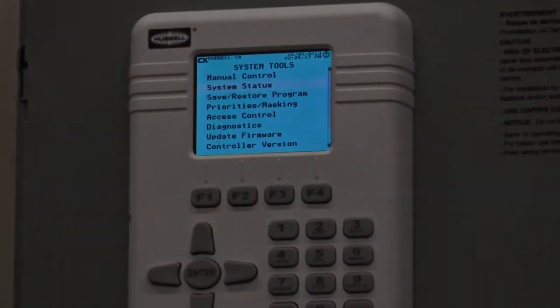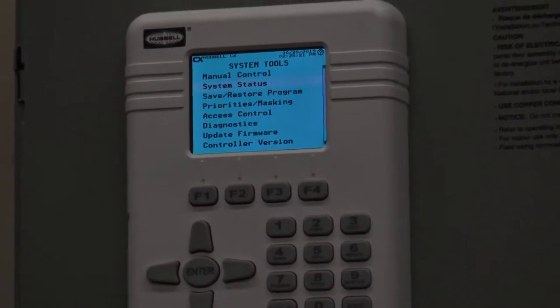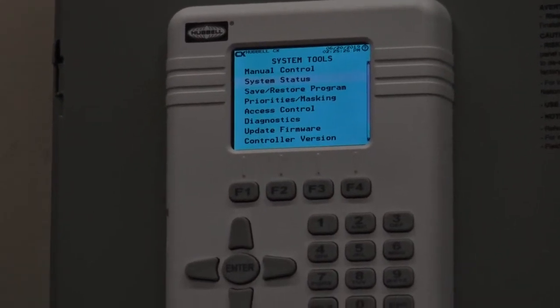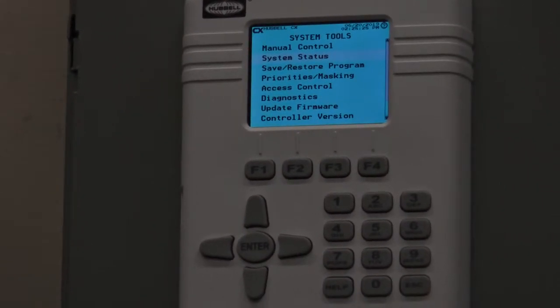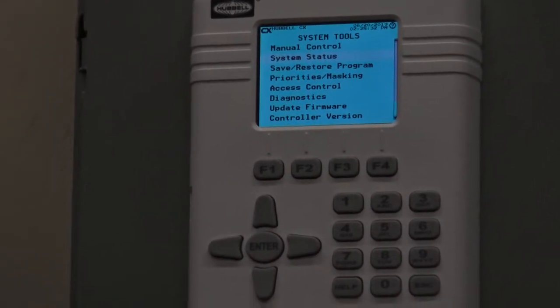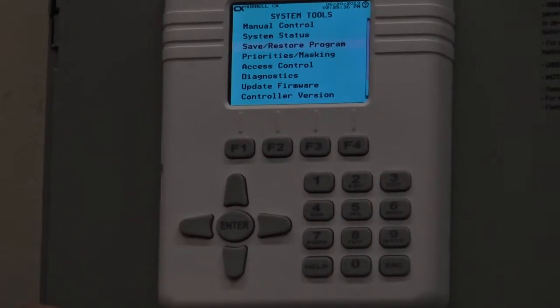And if you do have an issue and you call the 800 number, they might ask you to go into system status. Okay, tell me if that is lit or not. Maybe you got some lights that are on relay number 7 that aren't working. Hey, is the circle dark or not? If it's dark, that means the relay's closed or it should be closed. It's being told to be closed anyways.